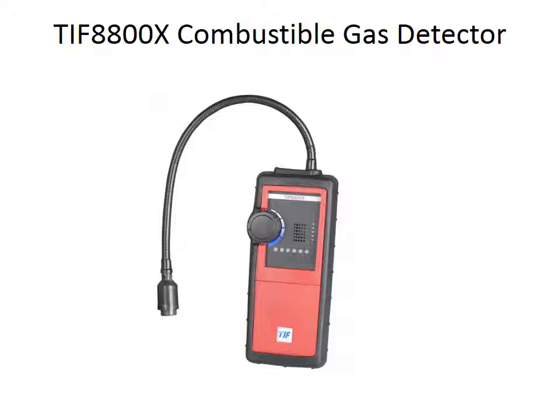The little dots on the bottom are LEDs. Those will light up as you get a concentration of natural gas. You will have some idea whether or not you're in a high concentration. So say you turn this on and you go into a room and all those lights are lit up, you're in a higher concentration of gas. It might not necessarily be telling you that you have an LEL environment. It's just telling you that you have a high concentration in that room.